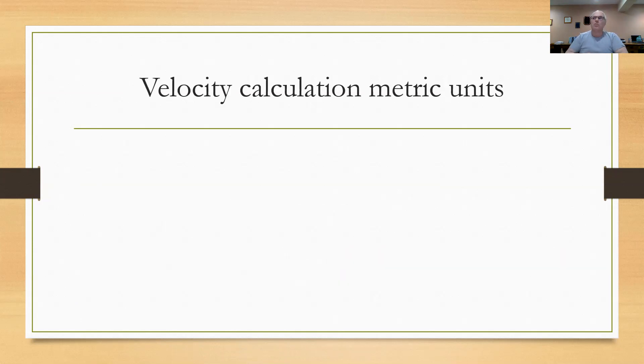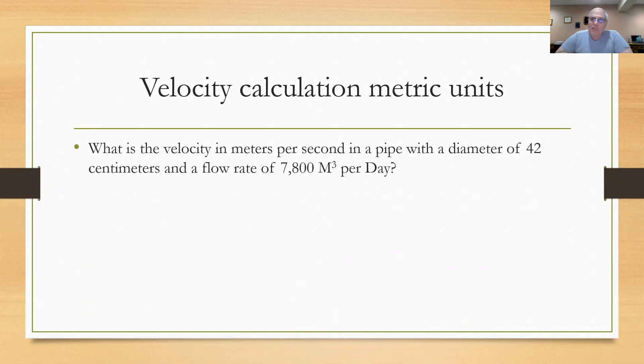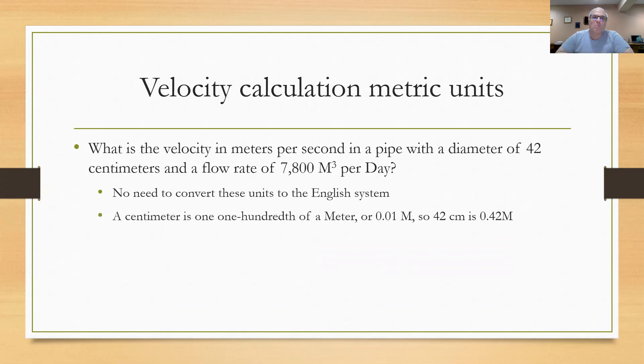Here's a calculation for velocity using metric units. This showed up on a class three exam in Ohio years ago. What's the velocity in meters per second in a pipe with a diameter of 42 centimeters and a flow rate of 7800 cubic meters per day? When you see something like this, don't be tempted to change metric to English units. Just stay in the metric units. It's a lot easier and you won't get mixed up. A centimeter is one one-hundredth of a meter or 0.01 meters. So that 42 centimeter diameter works out to 0.42 meters.